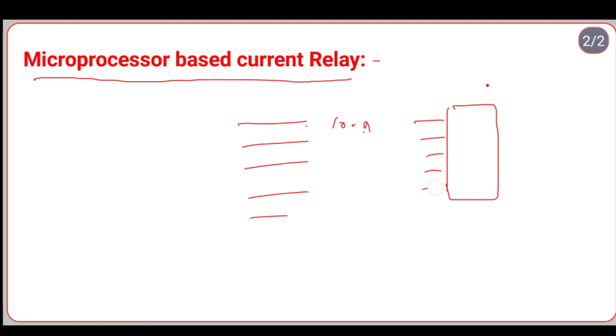Now, how does the microprocessor based overcurrent relay work? Using a multiplexer, the microprocessor can sense the fault current of a number of circuits. Fault current can be sensed by the use of a CT; normally a CT is used to sense the fault current. For all the circuits, the microprocessor can sense the fault current by using a multiplexer. A multiplexer has a number of inputs and one output.